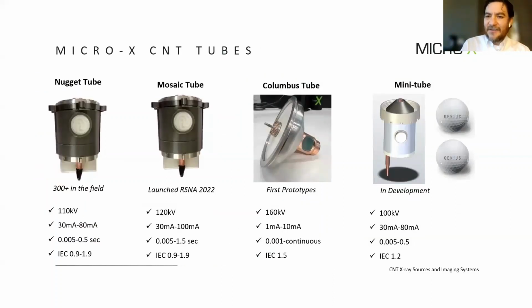To that end, we've developed 4 X-ray tubes to date as a company. Our first X-ray tube was 110 kV, went up to 80 mA on the anode, with half-second-long pulses, and varied between 0.9 and 1.9 focal spot. The next tube is similar to the first tube, but it goes higher. It goes to 120 instead of 110, goes to 100 instead of 80, and goes to longer pulses. So the second tube covers a broader range of exposures for digital imaging.